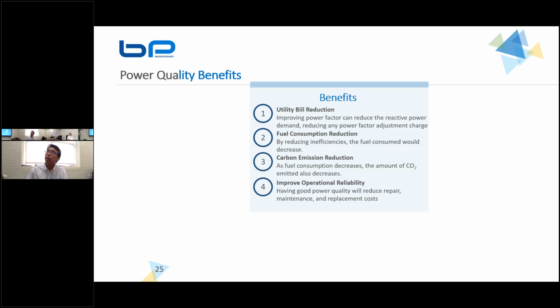So if you fix your power quality issues, there are several benefits, as we listed here. One is utility bill reduction, right? By improving your power factor, and depending on the utility, we can reduce the billing of reactive power demand or power factor correction charges. If you are using a generator or anything that requires fuel during operations, your fuel consumption can reduce because we're eliminating inefficiencies in the system that cause it to use more fuel. In turn, that leads into point 3, which is carbon emission reduction. As you use less fuel for your operation, there are less CO2 emissions in your system.